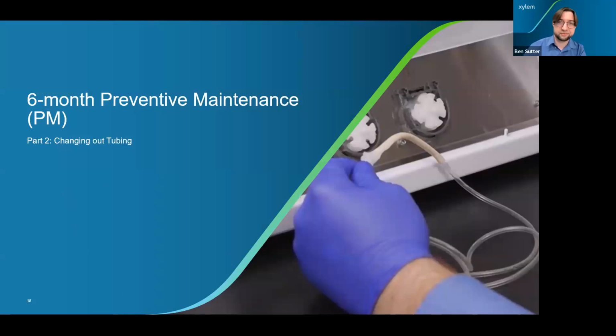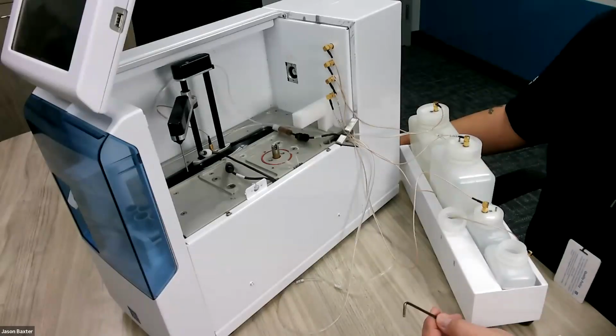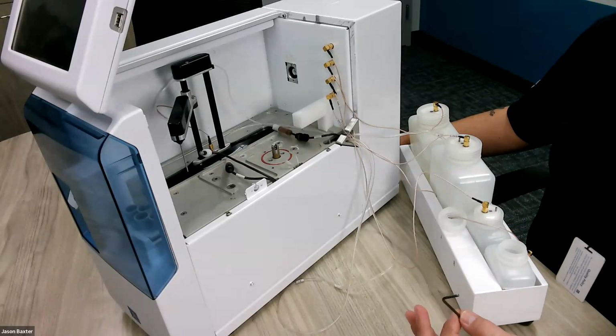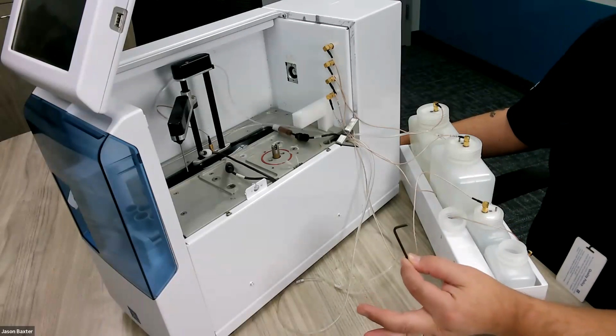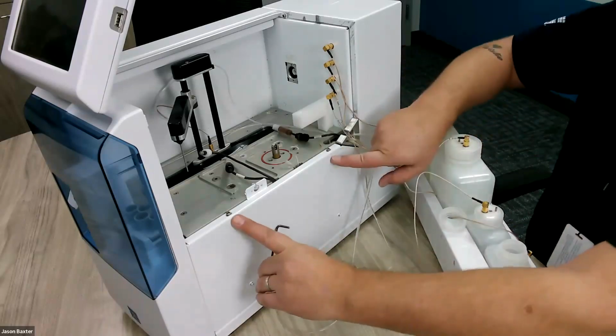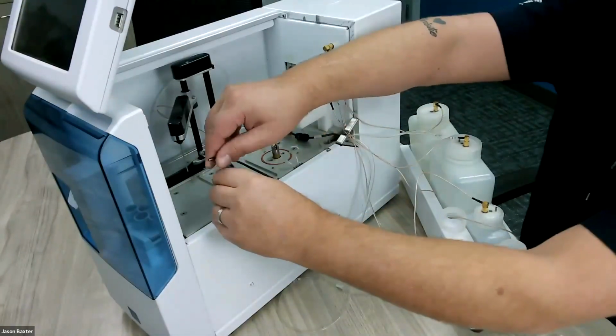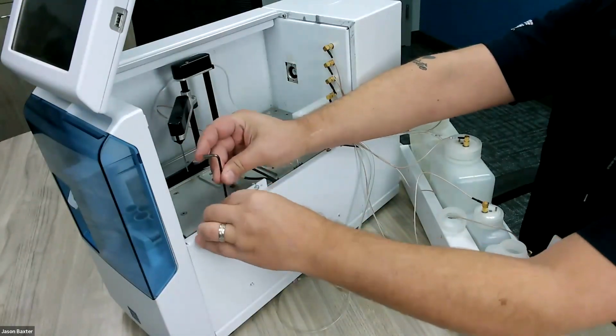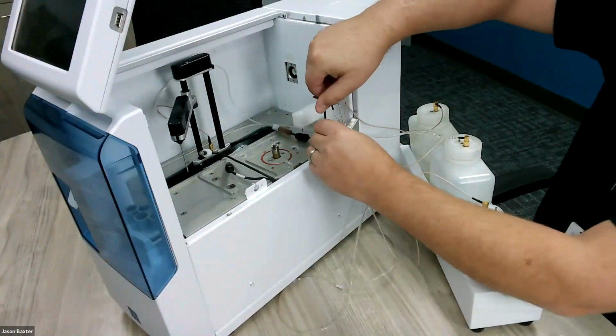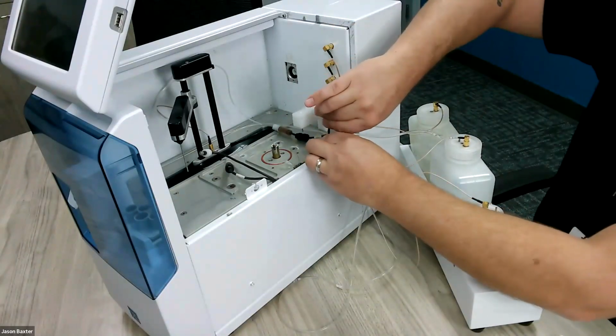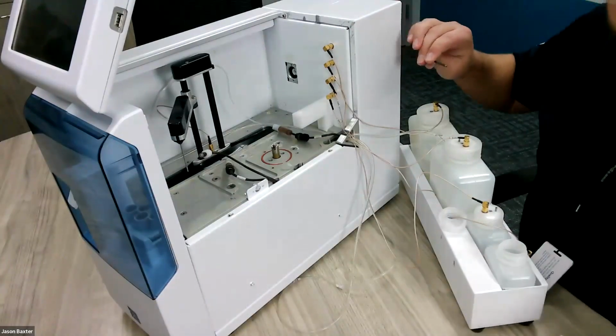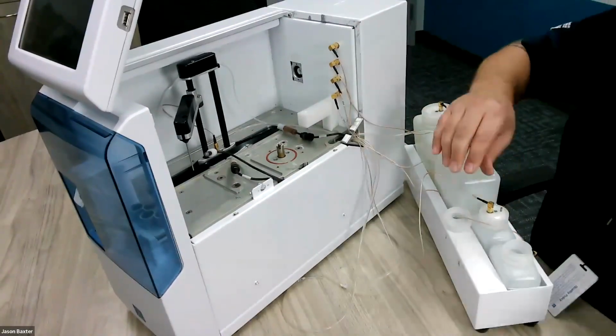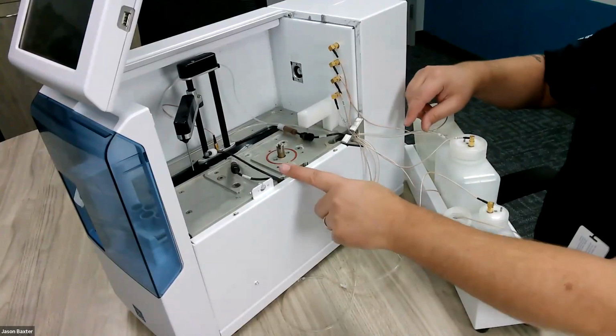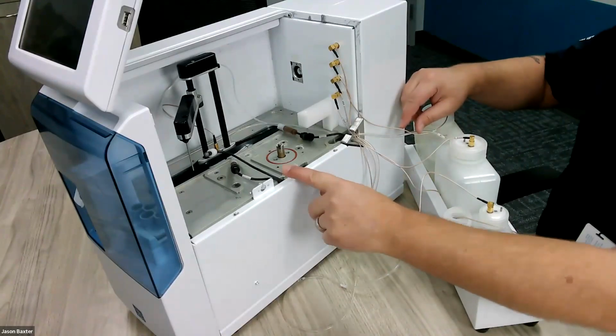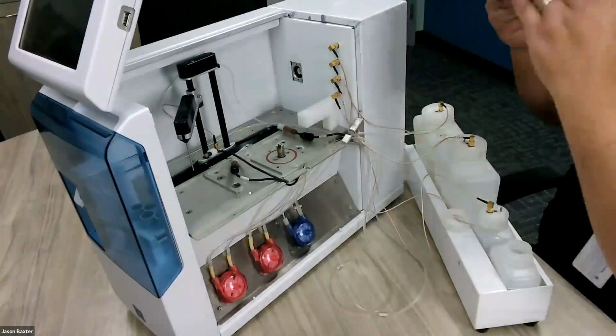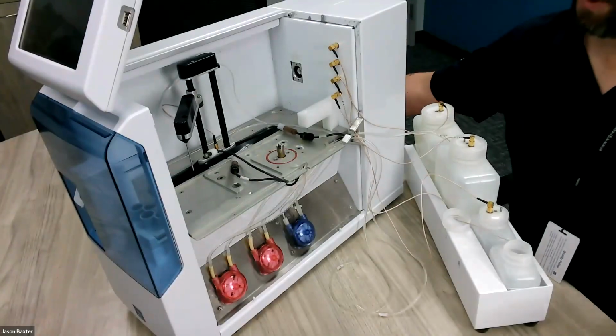Very well. Thank you, Ben. So to begin changing out your tubing, you're going to need your second Allen wrench, the larger of the two, the 7/64 Allen wrench. You have 2 bolts that need to be removed. You'll notice these are very short. Sometimes they like to disappear. Just, again, set them to the side where you can find them. Once you have your 2 bolts removed, you can grab this panel, pull it out toward you, and then lift up. And we now have all of the peristaltic pumps exposed.